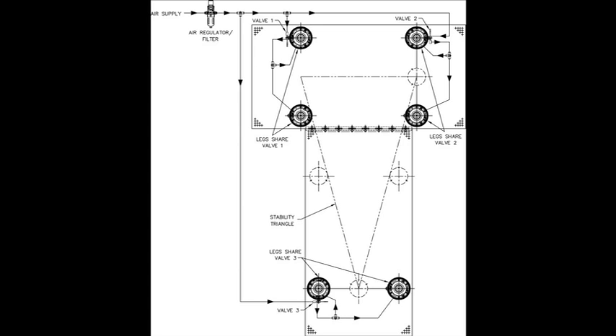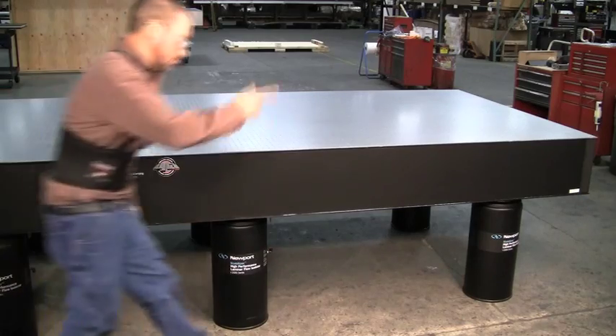Regardless of the size or shape of the table system, the basic components are the same. The main air supply should be passed through some type of air regulating filter. The ARF should feed only three leveling valves, and those leveling valves should be configured to supply the optimal number of isolators to create the largest stability triangle.